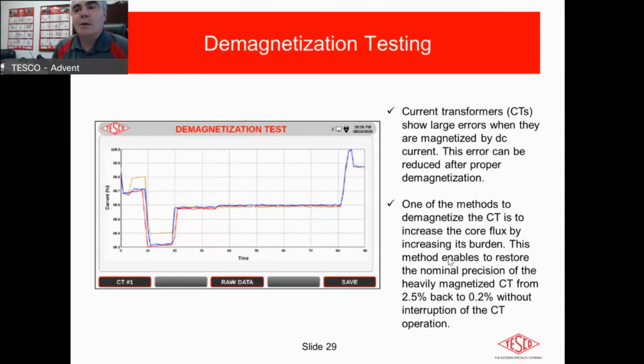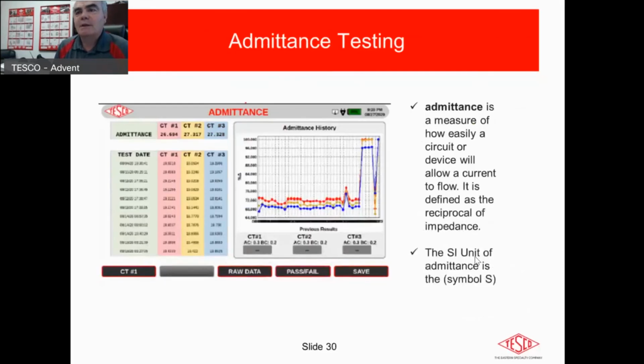We have seen brand new transformers directly shipped from the manufacturer be magnetized. So you cannot just assume that because you're getting them brand new that they are good to go. You've reviewed the test data from the manufacturer and everything is fine. It is possible that those CTs may arrive at your facility magnetized. So again, always the best practice. Okay. Go ahead, John. You want to jump on to the admittance testing?